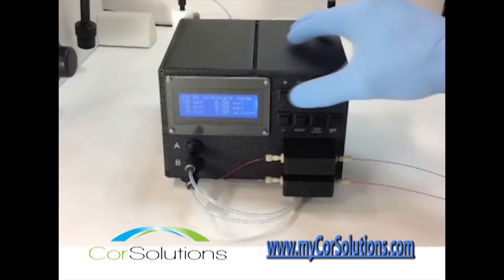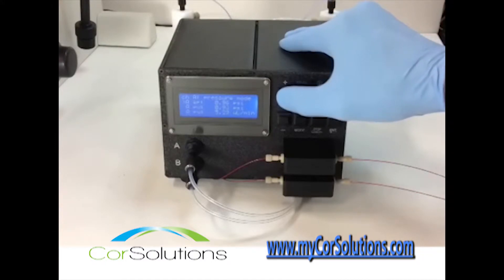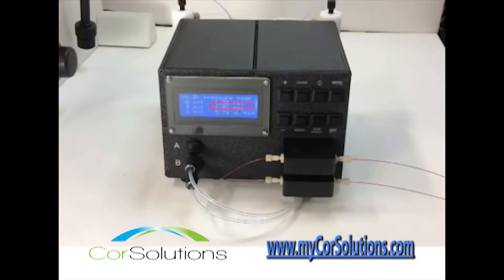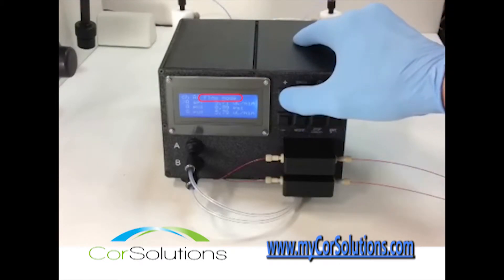This video demonstrates the use of the CorSolutions New Wave Pneumatic Microfluidic Pump. The New Wave delivers pulseless precision flow by pressurizing a fluid vessel with gas. CorSolutions' unique dynamic feedback control provides real-time measurement and adjustment of fluid flow rates and gas pressure.